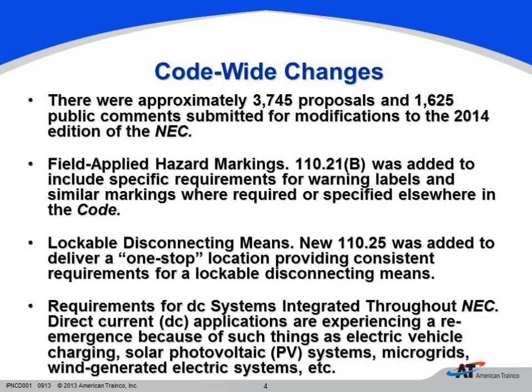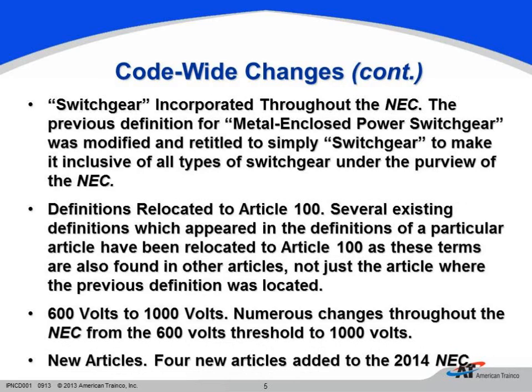Also, all the voltage and power that's measured between these conductors and ground will have to come down. It's going to have to have a label on there that identifies this shutdown equipment. So it's very important that we understand that some DC circuits here are definitely being affected by this 2014 code. Next slide gets us into definitions a little bit.